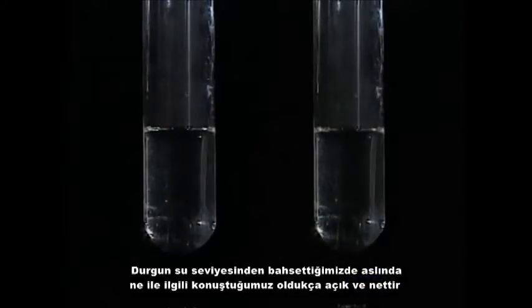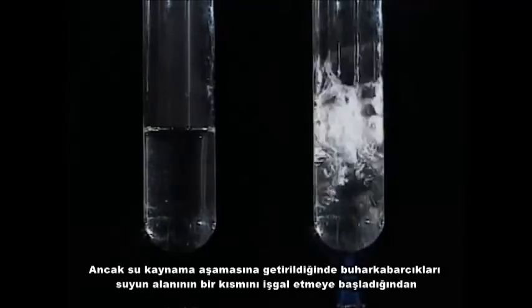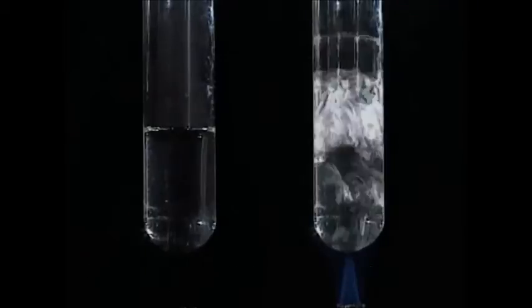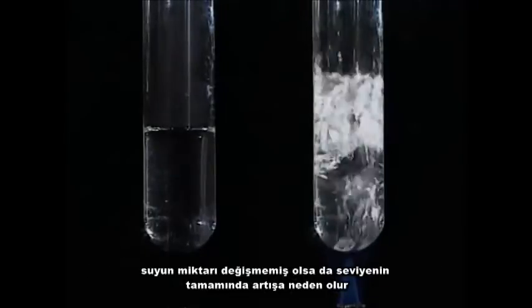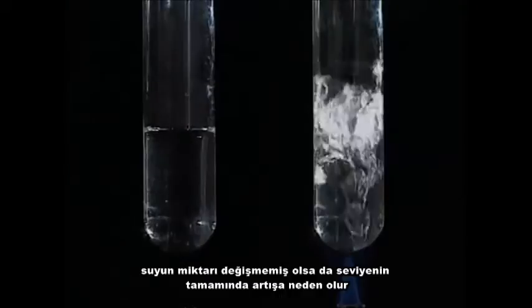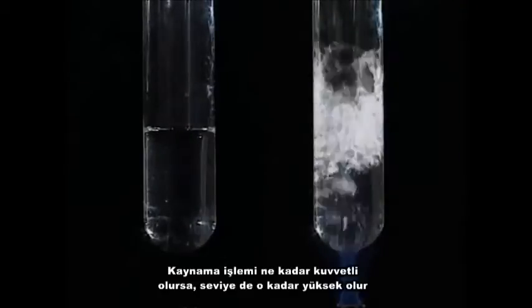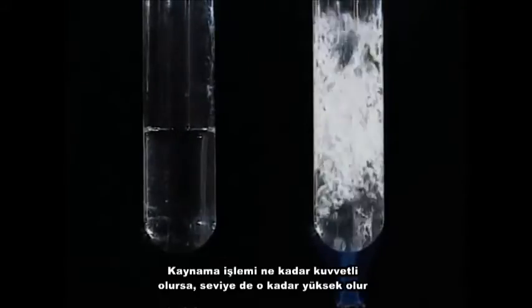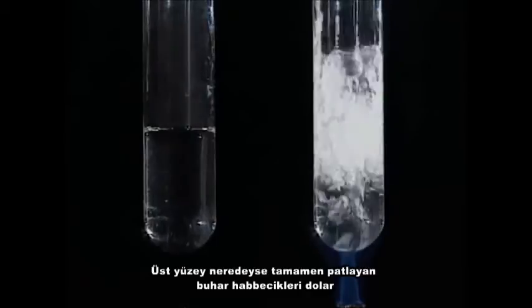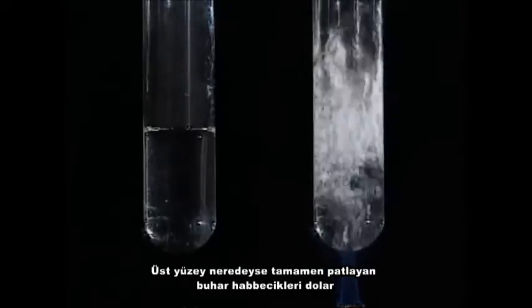When we talk about the level of still water, it is very clear what we are referring to. However, when the water is brought to the boil, bubbles of steam begin to occupy some of the water space, causing the overall level to rise, even though the amount of water hasn't changed. The more vigorous the boiling, the higher the level becomes. The upper surface consists almost entirely of large bursting bubbles, and inside a boiler, the thickness of this bubble layer can vary depending on the circumstances.